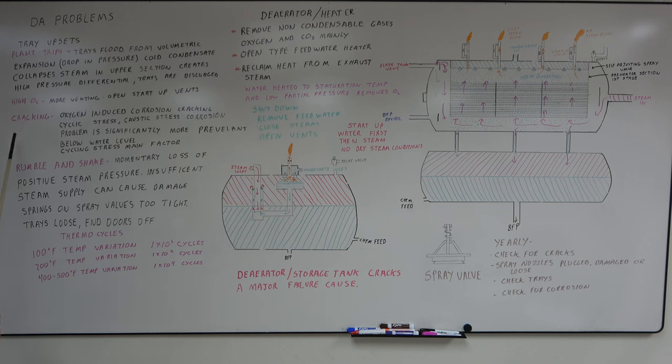Cracking is a major problem for deaerators. It's probably the number one thing people really need to be aware of. It can be oxygen-induced corrosion cracking from cyclic stress. It can also be caustic stress corrosion. The big thing is the stress in this from the temperature, steam, and water heating it. It can create quite a bit of damage cracking over time. A lot of the cracking is below water level in storage tanks. Cycling stress is the main factor.